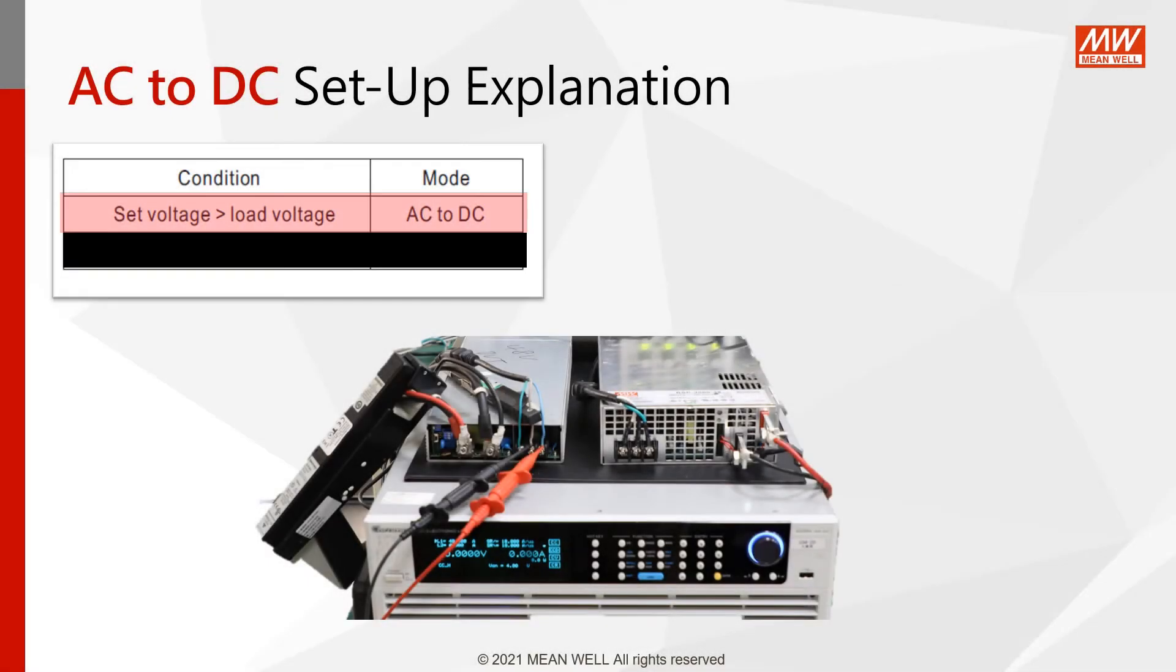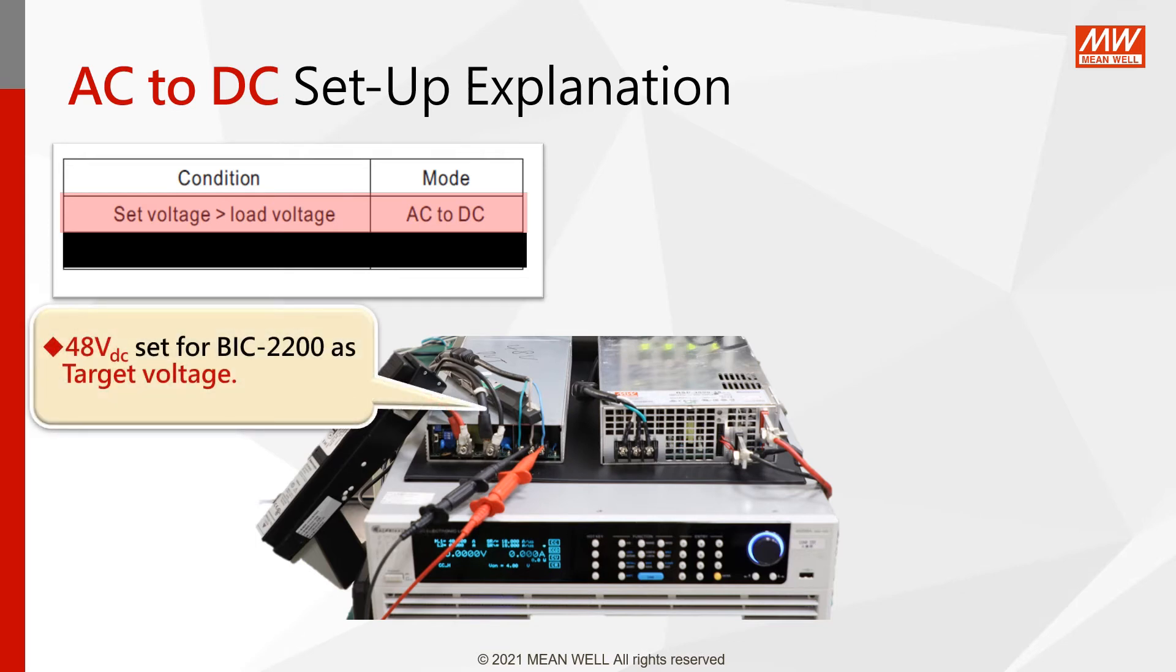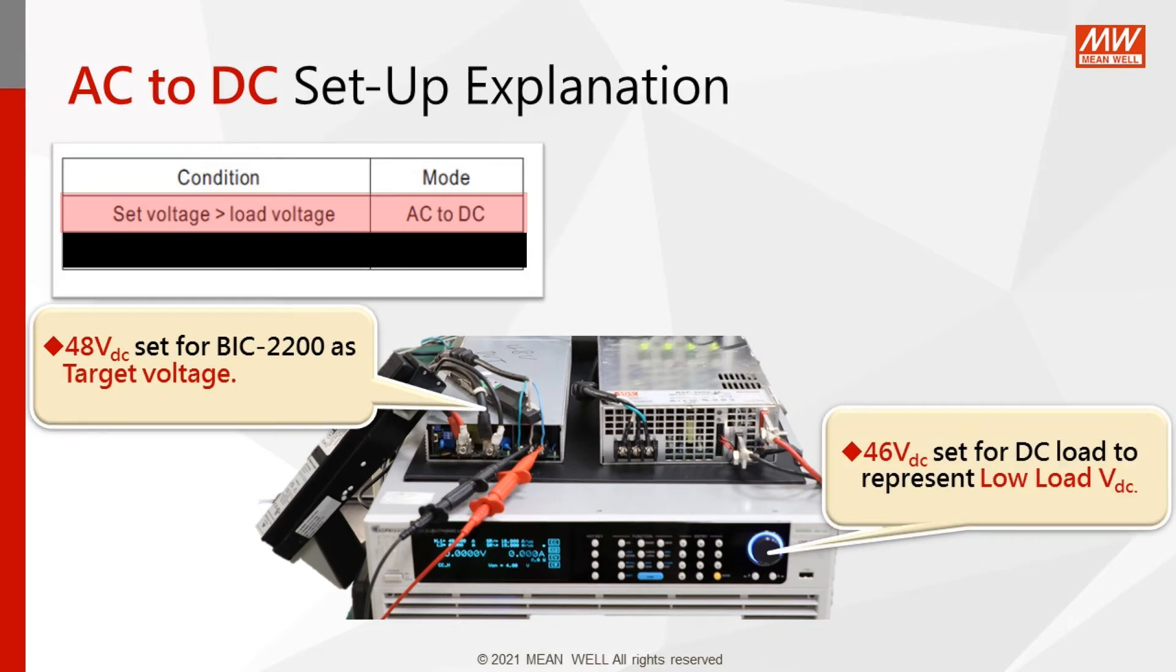Take BIC-2200, 48 volts as an example. Its default target voltage is 48 volts. When a battery with 46 volts or a DC electronic load set at CV mode and 46 volts is connected to the BIC, the BIC will convert AC to DC to charge the battery or feed DC energy to the electronic load as 46 volts is lower than the target voltage.